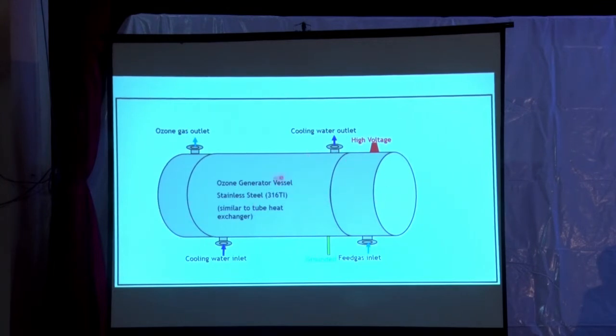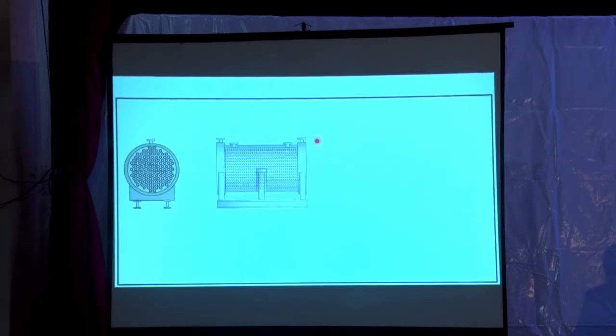During the ozone generation process, there will be heat generation. To dissipate that heat, we give cooling water, which is chilled water, at the inlet and outlet. This is a typical ozone reactor in detail. This is a generator. It has two sections, section 1 and section 2. In section 1, partially ozone will be converted, and the remaining oxygen is converted in the second section.